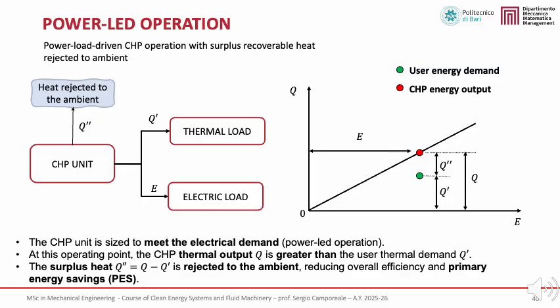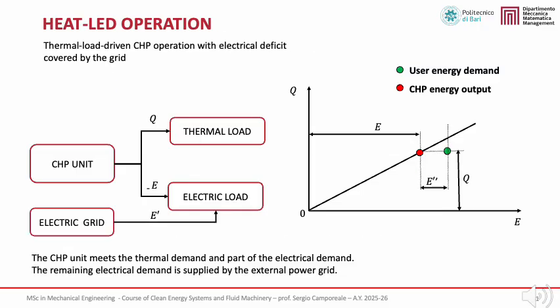Only part of the available heat is delivered to the thermal load, while the remaining share, indicated as Q double prime, is rejected to the ambient as waste heat. This condition represents an unfavorable operating mode, since unused recoverable heat leads to lower overall heat utilization and a reduction in the primary energy saving index. For this reason, EU CHP design guidelines recommend avoiding such operating conditions whenever possible through appropriate sizing, thermal storage, or additional heat sinks. We now move to heat-led CHP operation with an electrical deficit.